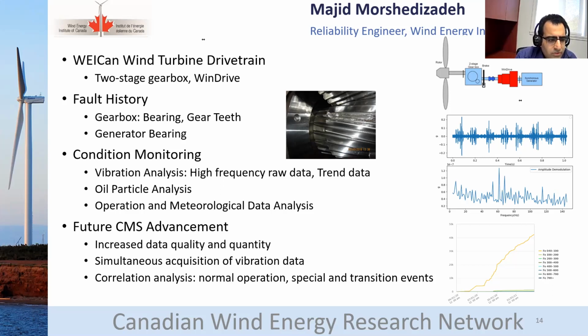and we do a lot of different analysis with these data, from extracting statistical measures from the time series to frequency domain analysis, something like simple FFT, or more complex wavelet or amplitude demodulation, Cepstrum, or empirical mode decomposition analysis. For example, in this picture in the middle on the right, there's the first mode of one decomposed signal of failure data, and below that you can clearly see the impacts of the failure. This is for a bearing failure, and then in the graph below, the amplitude demodulation of the signal points to the inner race fault frequency of the turbine that we saw.